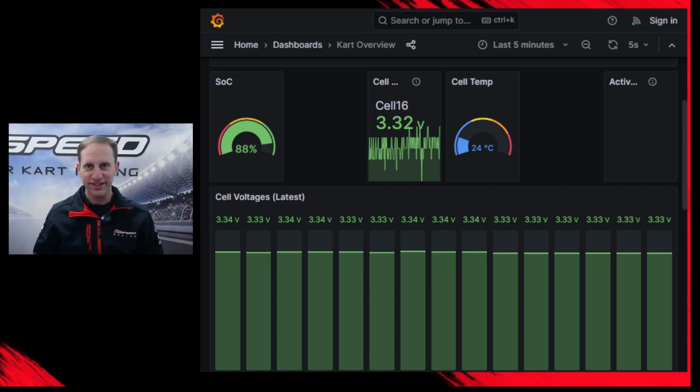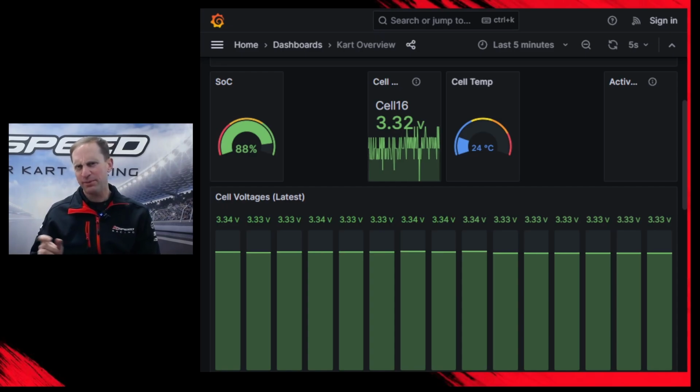In fact, in testing and racing environments and the endurance races we've been running, we see the batteries float between 40 and 45, maybe 50 degrees Celsius. We may push that limit a little bit during the 12 hours, but we're not anticipating seeing 70-degree temperatures like we did before. And that is great news for everybody.